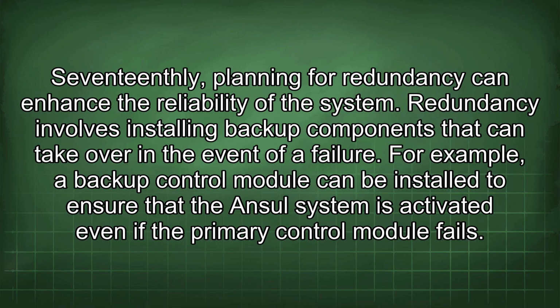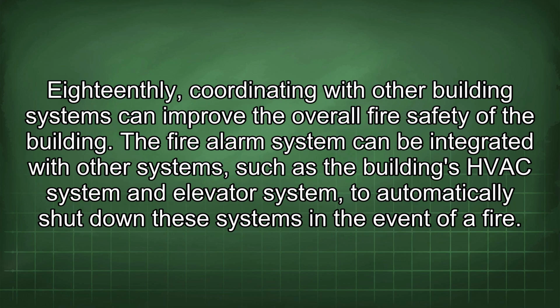17thly, planning for redundancy can enhance the reliability of the system. Redundancy involves installing backup components that can take over in the event of a failure. For example, a backup control module can be installed to ensure that the Ansul system is activated even if the primary control module fails. 18thly, coordinating with other building systems can improve the overall fire safety of the building.